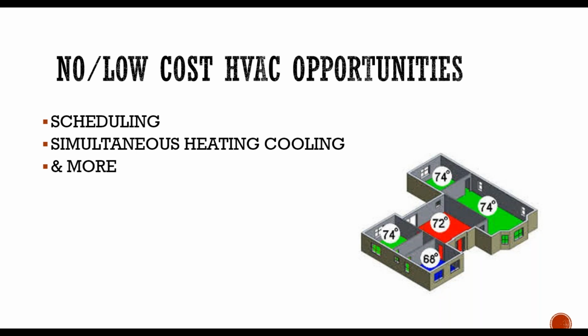We just did an energy audit at a large Baptist church, and they had a 134-ton cooling unit operating 6 offices, but it was also part of the children's room. So every day they were turning on 134 tons of chiller capacity, which cost them $35,000 a year. If they're able to replace that and minimize the use of that chiller only to when it's needed for the children's ministry, which I think was 2 days a week, and maybe install 6 VRF, which is variable refrigerant flow, that would cost them about $6,000 to install and only cost them $1,500 a year in energy to use. So you're looking at almost a $28,500 difference in that strategy. So again, just thinking outside the box.